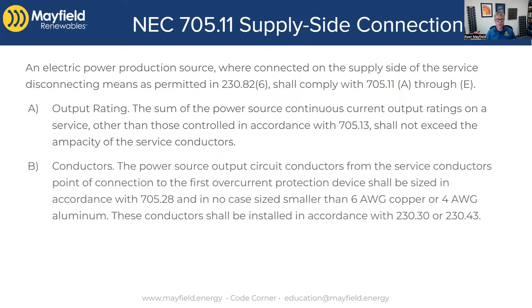705.11b also has an image here. This is one that over the years was never directly referenced, so it's nice that we now have this very distinct and direct reference. What it's saying is that the size of the conductors from the point of interconnection to the first overcurrent device must be sized in accordance with 705.28 — which is basically the same as how we size our inverter output circuit conductors. Not a lot new there, just a different reference versus 690. But it says in no case smaller than 6 AWG copper or 4 AWG aluminum, and we have to install it per service rules. Some inspectors would call this out under 230 and others would not, so it's nice to have this definitive section.